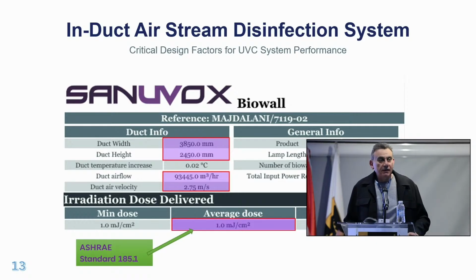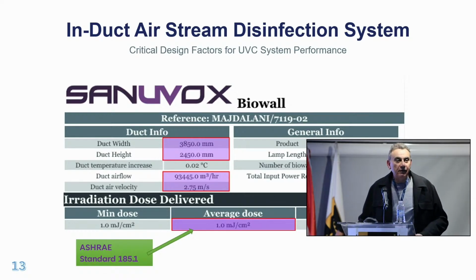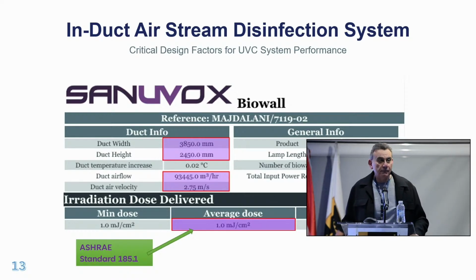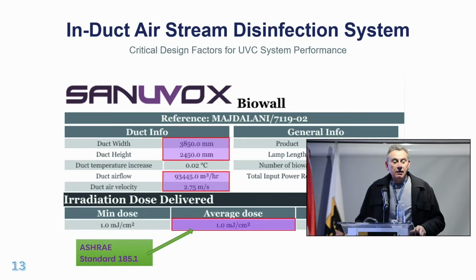So here we input the width of the duct, the plenum is 4 meters wide and 2.5 meters high. The amount of air we need to move, which is almost 55,000 CFM, or 95,000 meter cube per hour. We had 4 air handling units like this. The lowest air velocity we could achieve is 2.75 meters per second because of the size of the plenum.